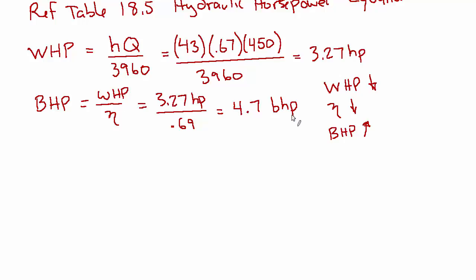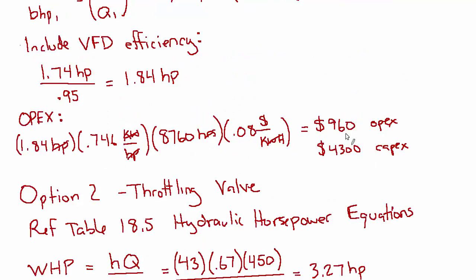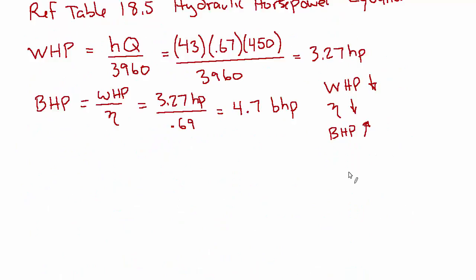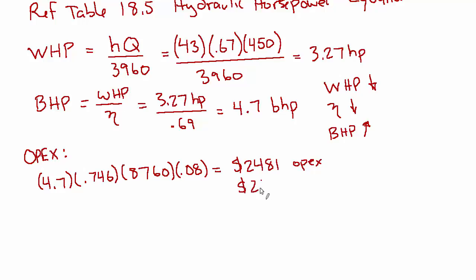Okay. So now that we have our new BHP, again, we're neglecting electrical efficiency. So we're going to assume that this is just the power that we need. And we can go through the same sort of formulation to find the OPEX as we did in option one. And I'll skip the units on this one because it's going to be all the same parameters going in. We have 4.7 for the horsepower times 0.746 times 8760 hours times 0.08 for cost per kilowatt hour. And that works out to 2481. That's the OPEX. And just for completeness, the cost was 2625 up front.